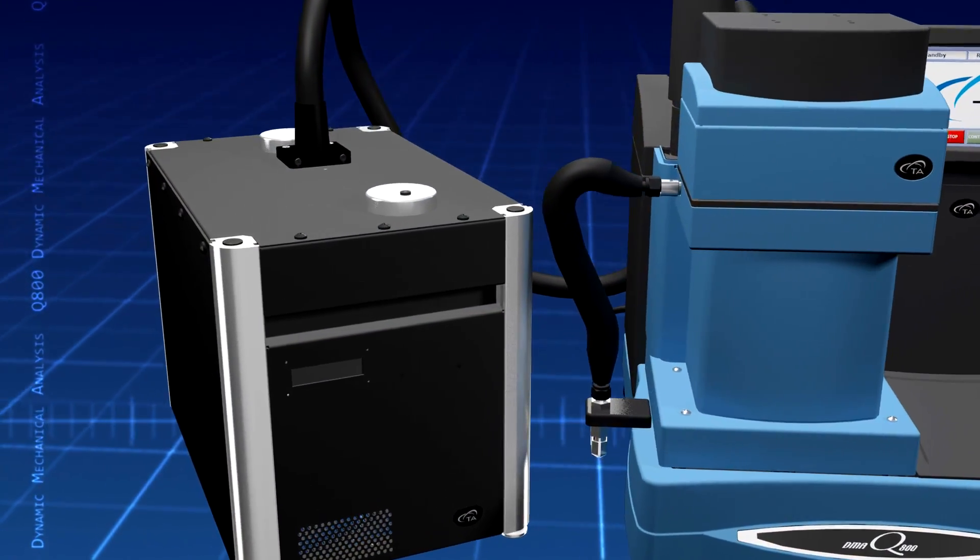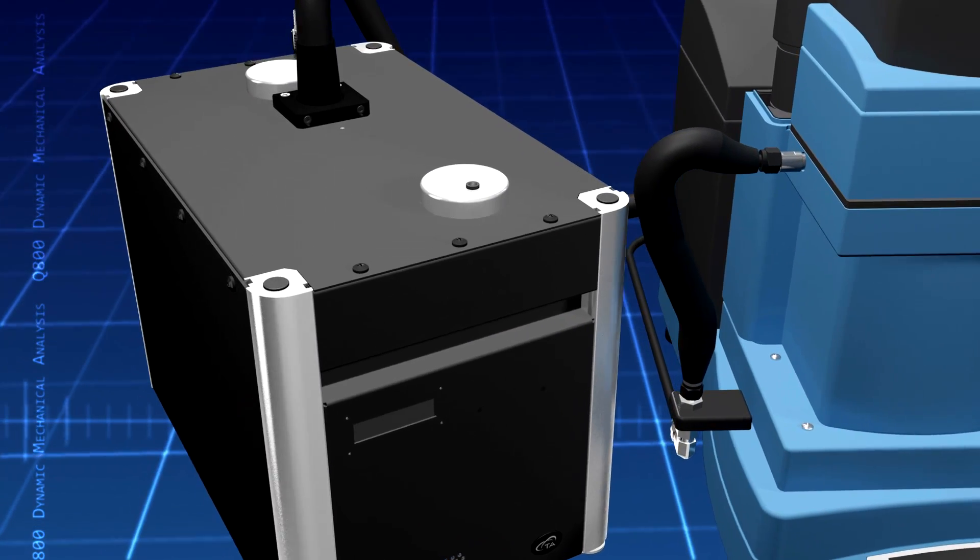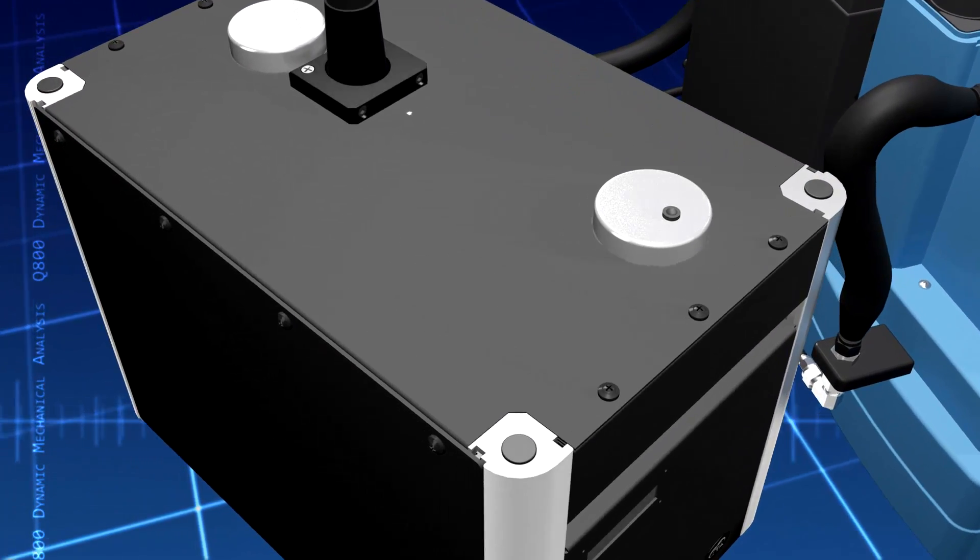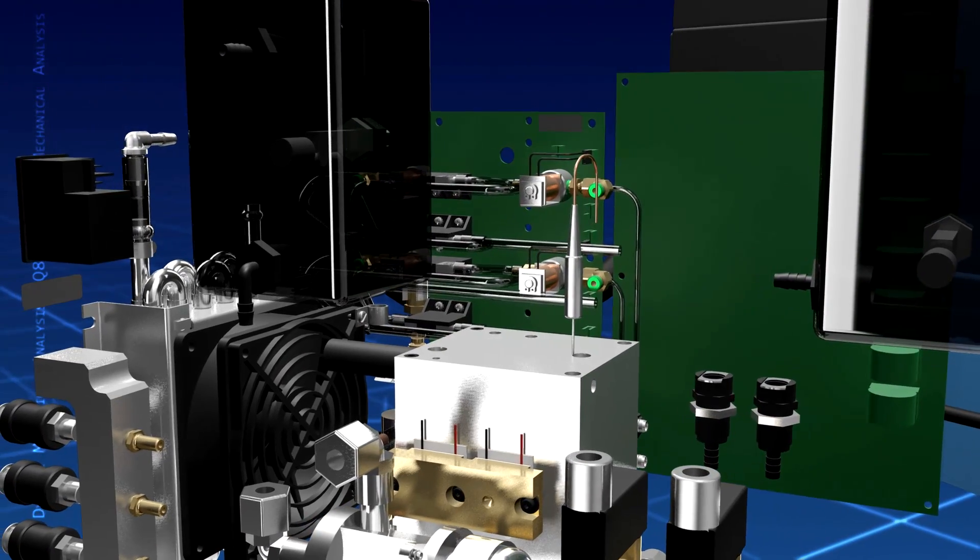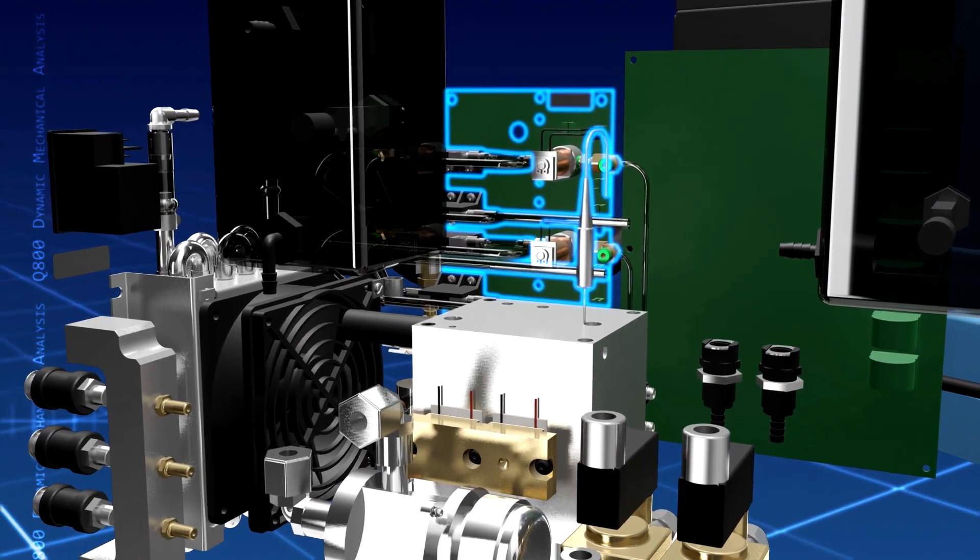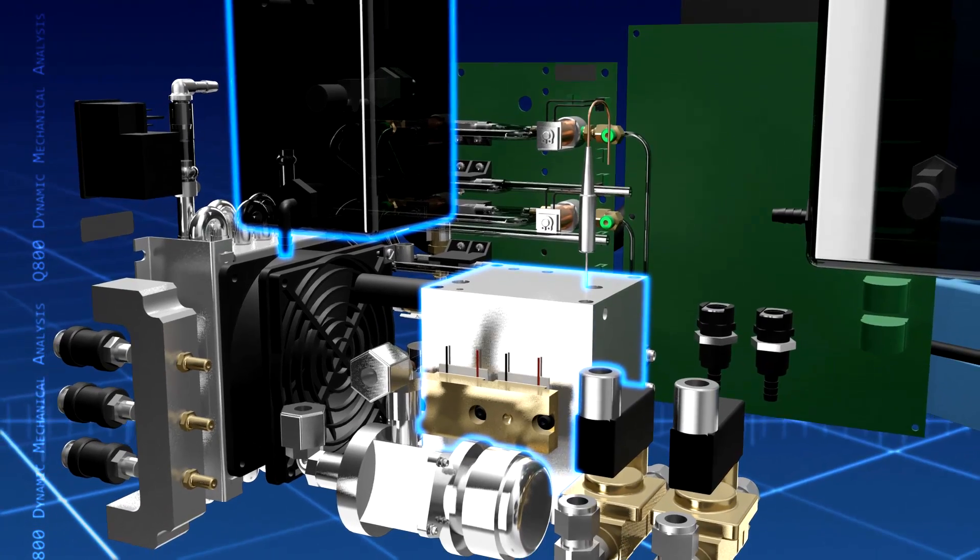It ensures precise and accurate RH control through an innovative humidity generation system consisting of precision mass flow controllers and an integrated saturator with a bulk water reservoir.